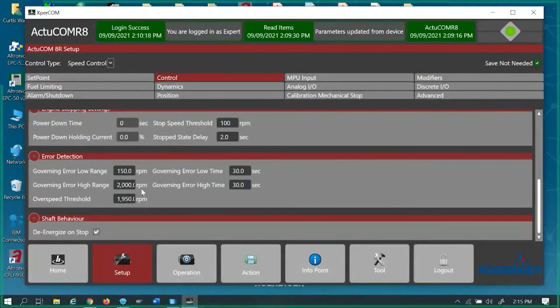Stop state delay. Governor error, here's where your RPM and times are. I believe the way this reads, if it stays at say 150 RPM difference for a certain amount of time, it's going to shut you down. So if you're supposed to be at 500 RPM and you're running at 300, it's going to start counting 30 seconds. If you don't get it up within 149 RPM of that set point, it's going to shut you down. Governor high error range, same thing. Overspeed threshold, that's just where you put your overspeed in.